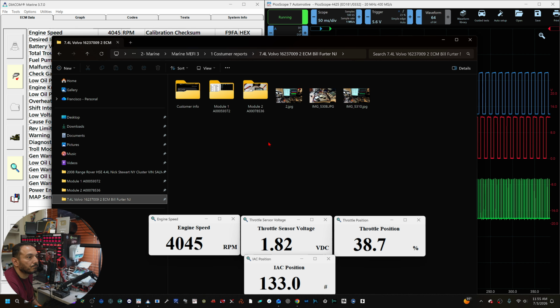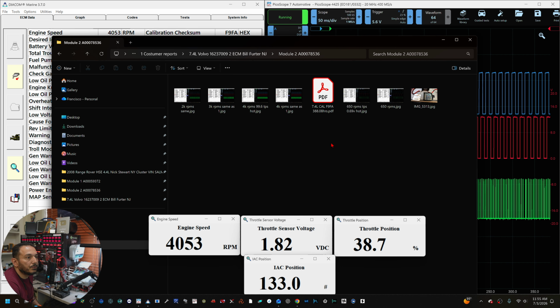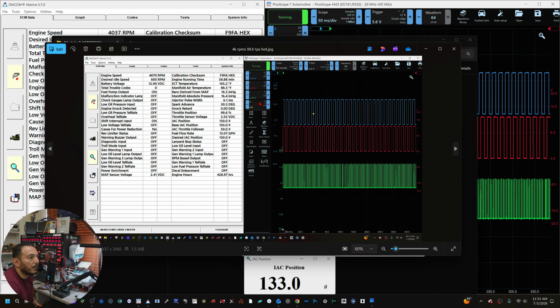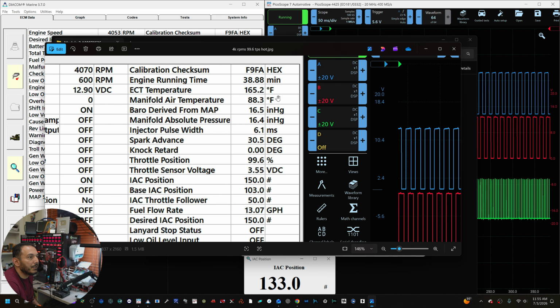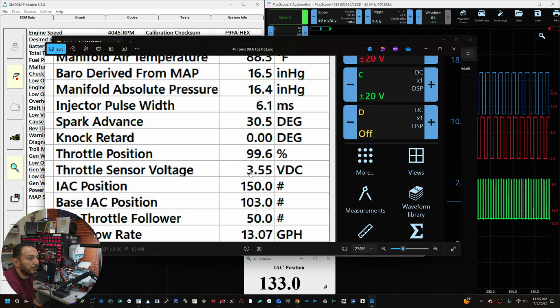Right here, number 2, 4,000... 38 minutes. Okay, so we still might need a little more time. You see, guys, right here, 38.88 minutes, and that's when it glitched out. And then you see 99.6 at 3.55 volts. So we lost actually 100th of a volt, which is changing the IA, because look at the IA position in that one, 150.